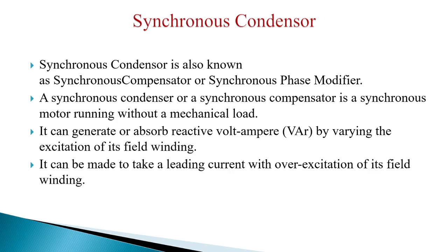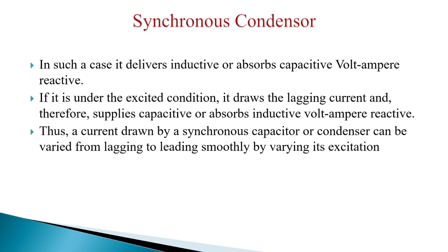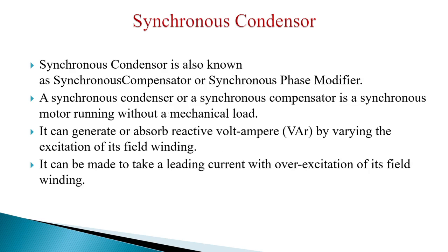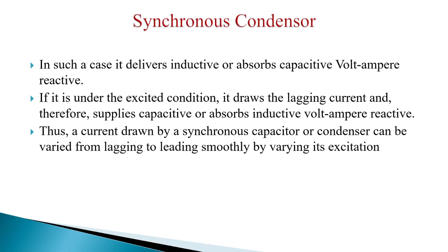It can be made to take a leading current with overexcitation of its field winding. In such a case, it will deliver inductive or absorb capacitive volt ampere reactive. If it is under the excited condition, it will draw the lagging current and therefore will supply capacitive or absorb inductive volt ampere reactive.